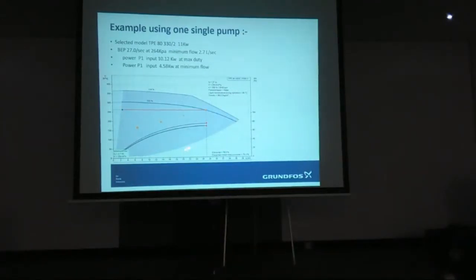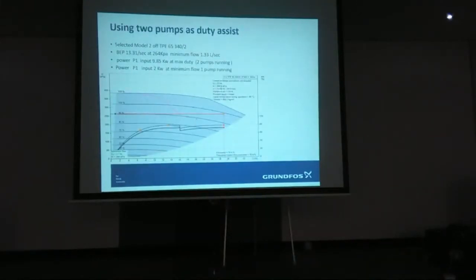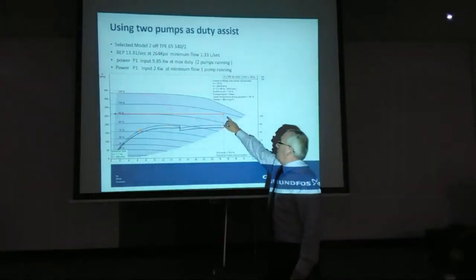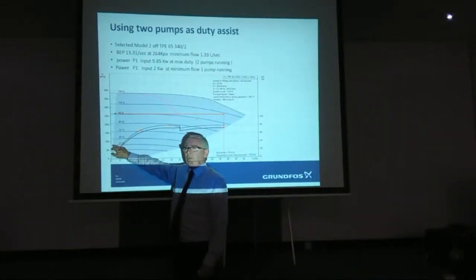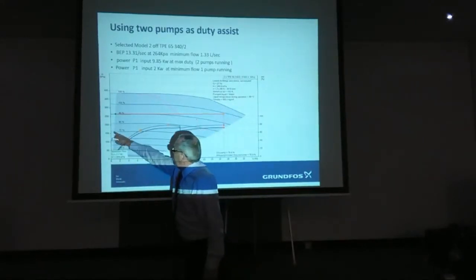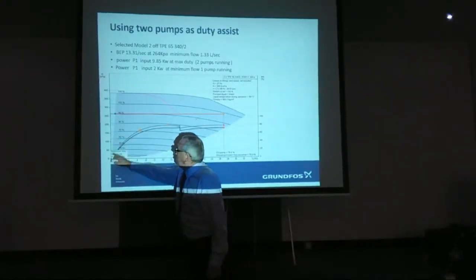It would absorb that, but it's not on that one, it would be on the next one. But if I used more than one pump, it's the best efficiency point of two pumps, which is now reduced from 2 point something to 1.1. So by going for multi-pumps, I've achieved the maximum demand and the minimum requirement. That's based on constant pressure, obviously. If we were working out in the sticks somewhere, you'd be working down here, and the flow rate can reduce even more. If that was there, that's about 0.7, something like that.